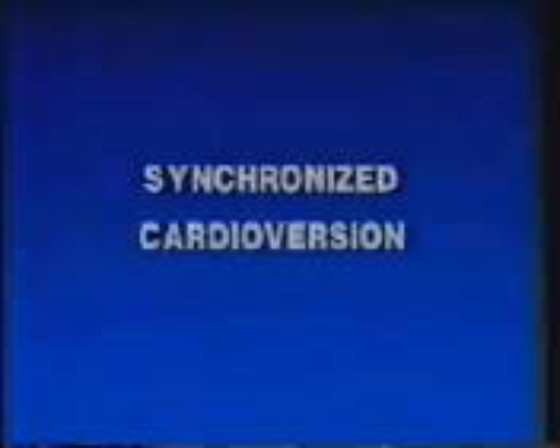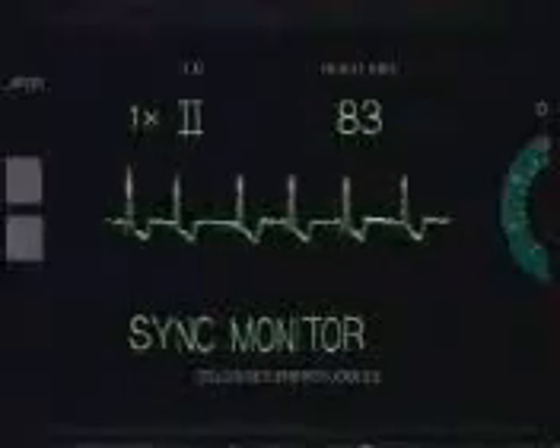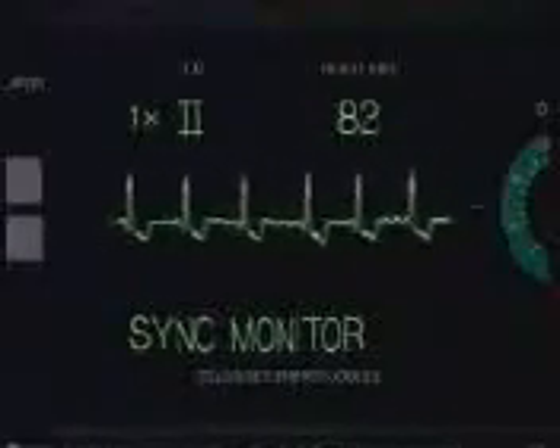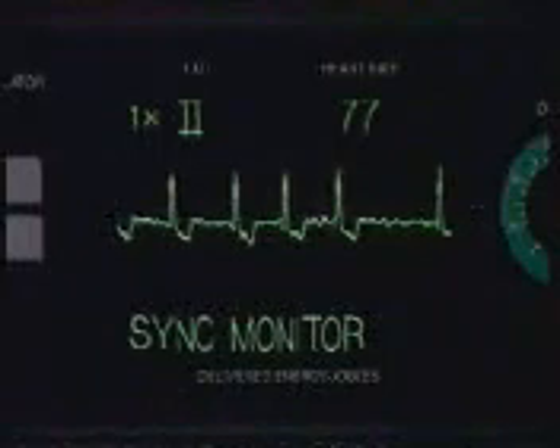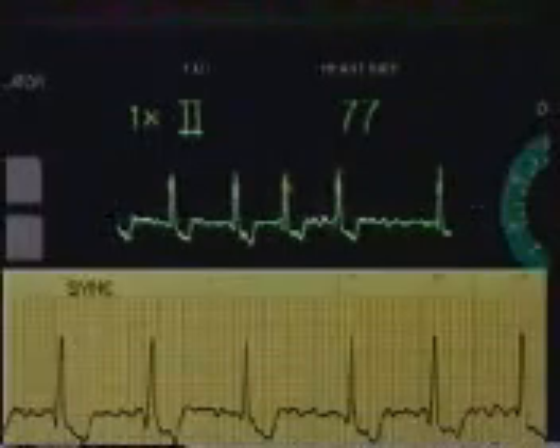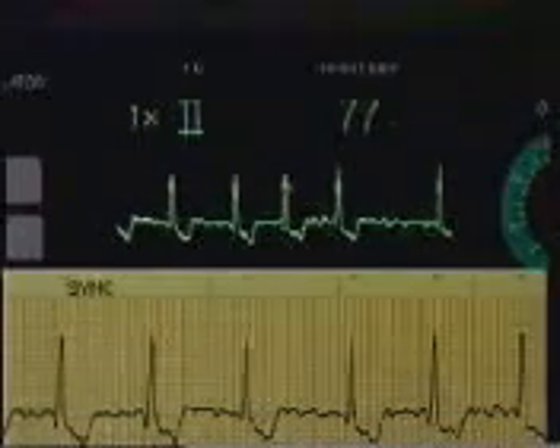Synchronized cardioversion. To perform synchronized cardioversion, first press the sync button in the monitor on position. Sync monitor will appear on the screen. A sync marker or intensified dot will appear on each R wave as well as a mark above the waveform on the ECG recorder strip.